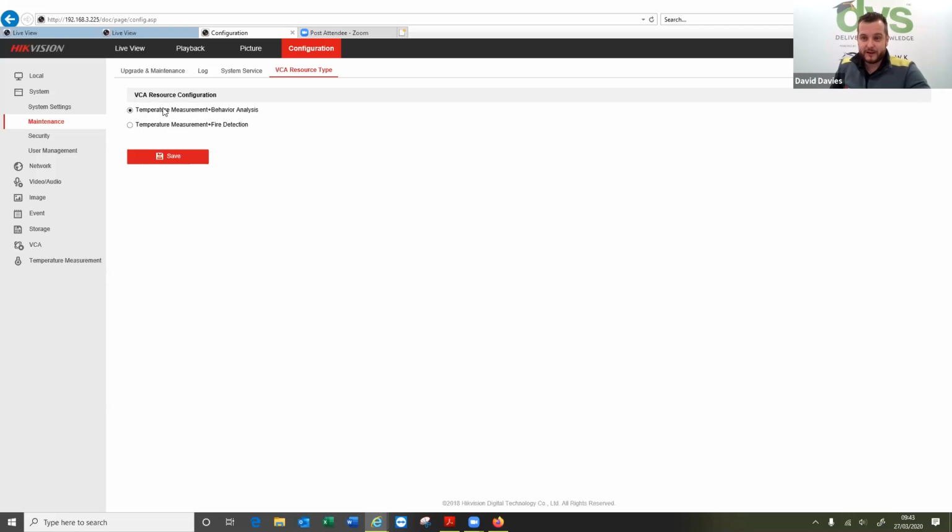So with the fever stuff, if you are interested, the default accuracy is at 0.5 degrees. But if we use our black box heat emitter unit, it'll bring the accuracy down to 0.3 degrees, but there is a cost associated with that unit. So the cost to get the 0.3 enhanced accuracy might be something that you don't want to do and you want to offer the cost saving function instead. But that'll be a separate video on Monday, so keep an eye out for that.